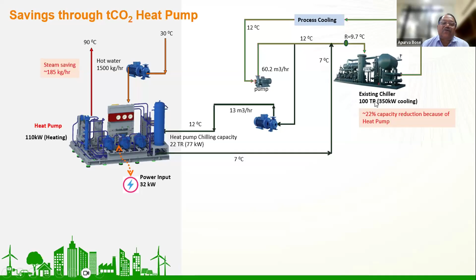In this entire setup, the power being consumed by the compressor is 32 kilowatt, and in turn we are getting heating of 110 kilowatt and cooling of 77 kilowatt. If we do the calculation further, this is also providing a steam saving of almost 185 kg per hour. Since this is a 100 TR unit already there, it is getting an additional 20 TR of further cooling, so there is a 22% capacity reduction because of the heat pump.